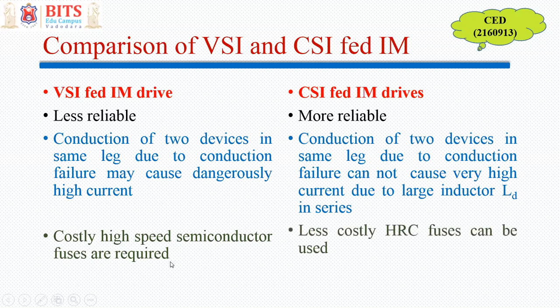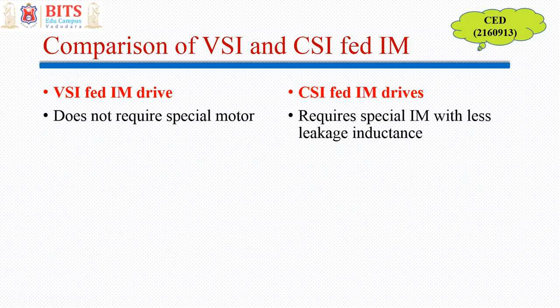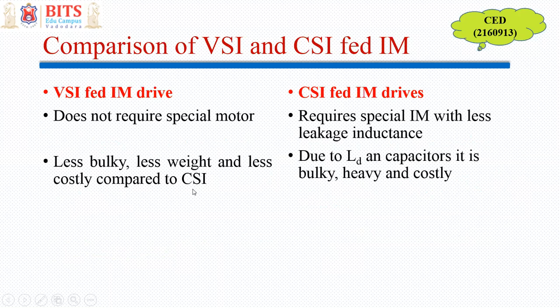Due to very high fault current in VSI, you require costly high-speed semiconductor fuses, while in CSI you can work with less costly, relatively slow HRC fuses because the current magnitude is not that high. CSI requires a special induction motor with less leakage inductance, because large leakage inductance produces large L·di/dt voltage spikes which are dangerous for insulation. VSI-fed induction motor drives are less bulky, lighter, and less costly compared to current source inverters, which are bulky, heavy, and costly due to the large inductor and capacitors.